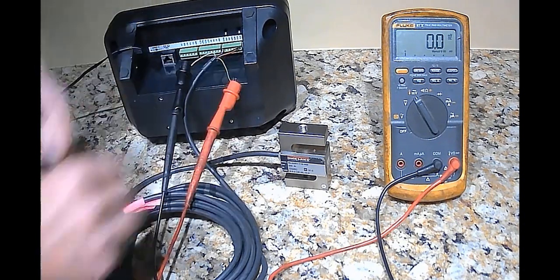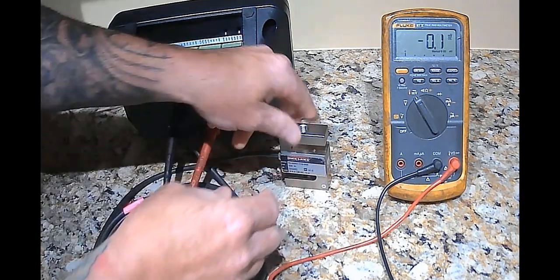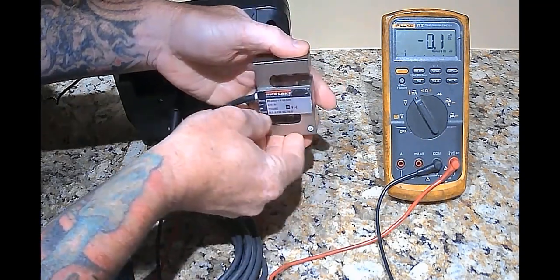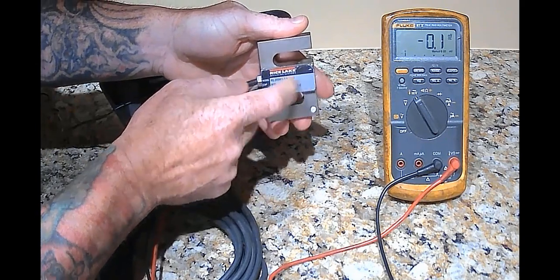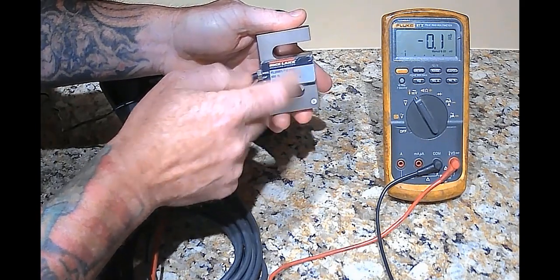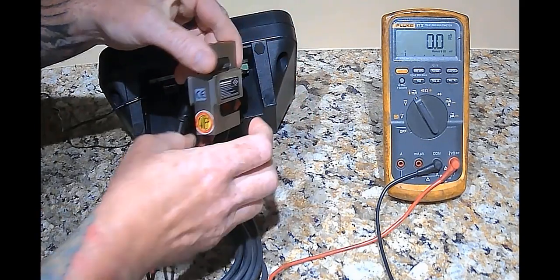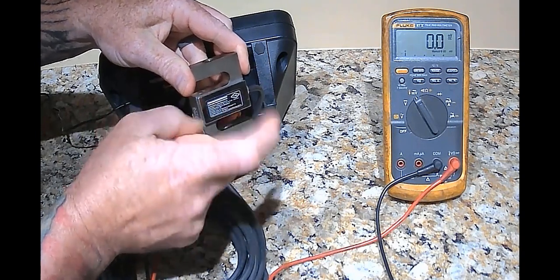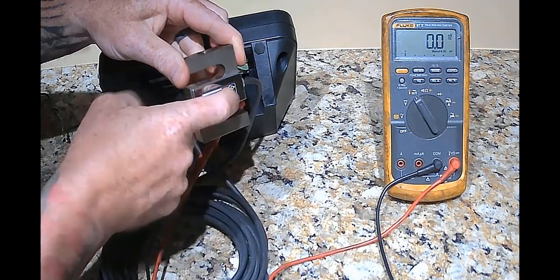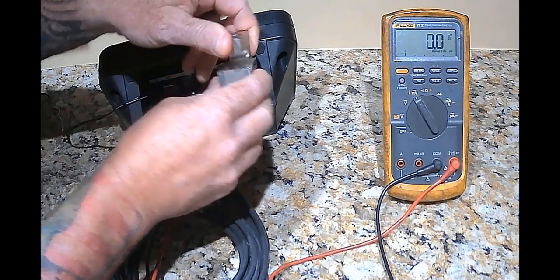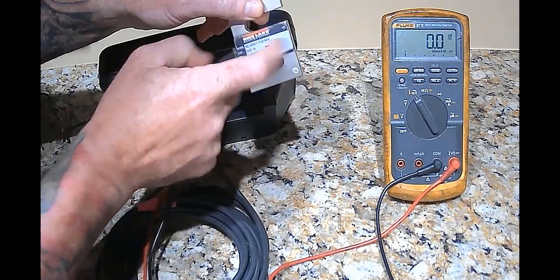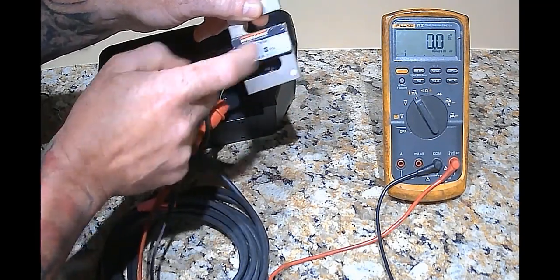Next, lightly tap on the load cell with a small rubber mallet or your hand for smaller cells to mildly shock it. Exercise extreme caution not to overload low capacity cells. Watch the readings during the test. The readings should not become erratic. They should remain reasonably stable and return to original readings. Continue until all cells have been tested.